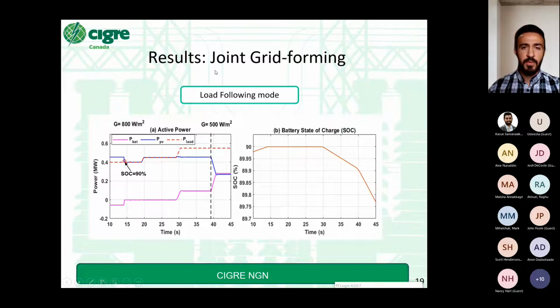Here we have the results for the load following mode when we have the joint grid forming. At the start here, we can see that the battery is charging, and as it reaches SOC 90%, which is set to be the SOC max, the PV will enter load following mode and start tracking the load in order to push the battery into idle state.